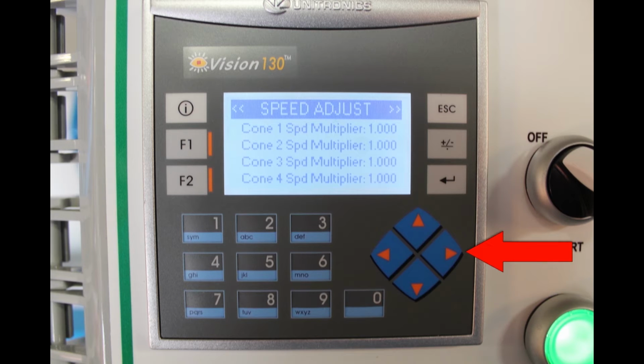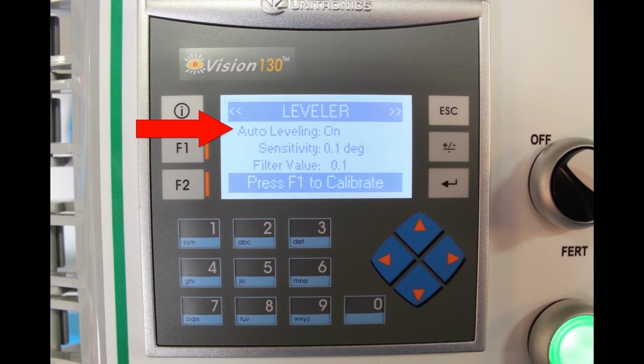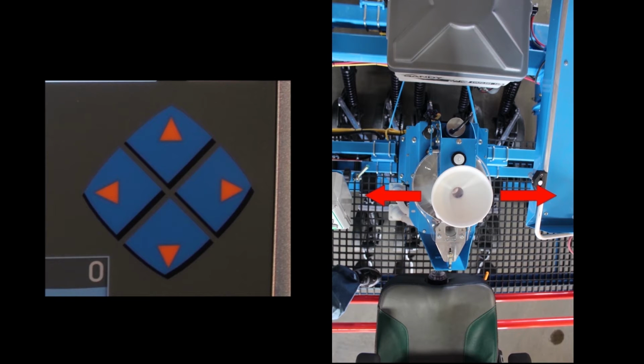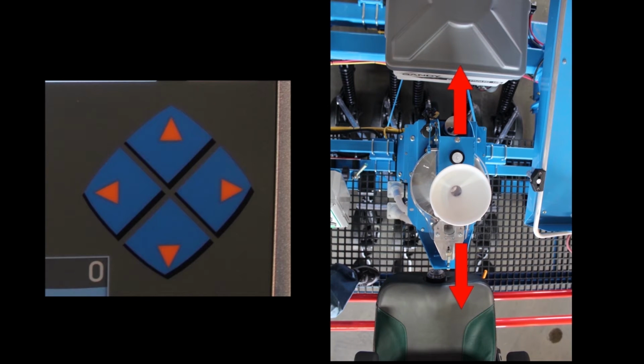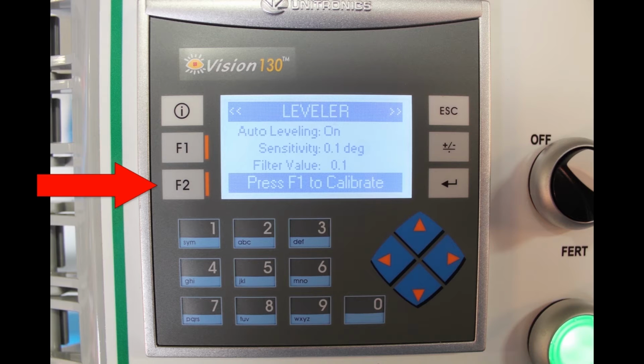Pressing the right directional button again takes us back to the ready screen, unless your machine is equipped with a leveling system. If it has a leveling system, press F1 to calibrate it, then use the directional buttons to move the cone until it is level with the bubble level indicator. Pressing F2 saves the calibration.